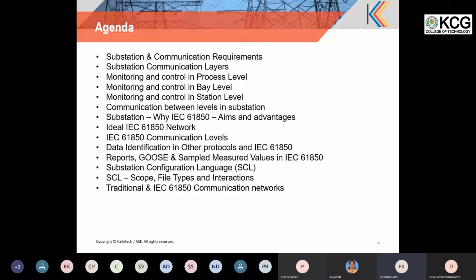Okay. So these are the agenda items for the first session. We will start with the basics like a substation, the communication requirements, and the different layers of communication on the substation side. Then moving on to process level, bay level, station level, communication between these layers, and why 61850 is a future-proof standard, and the importance of 61850. Then the 61850 network, different communication levels, the difference between other protocols and 61850, reports, GOOSE and sampled values of 61850, and substation configuration language, which is nothing but an XML representation of the data in terms of 61850. Then its scope, files and interactions, and traditional and 61850 communication networks. This is the agenda of the first session.